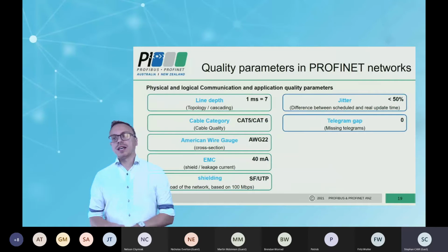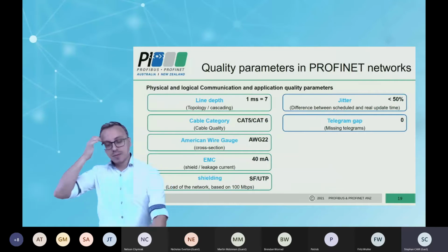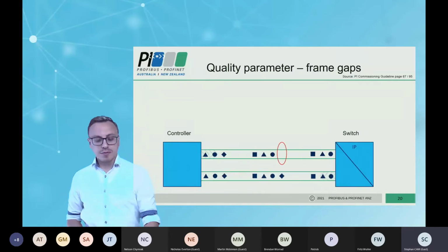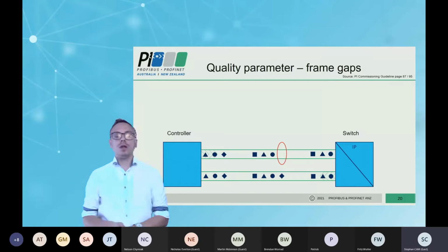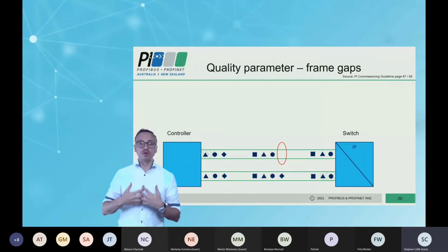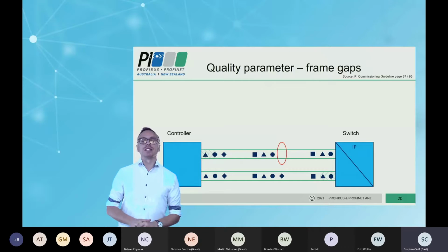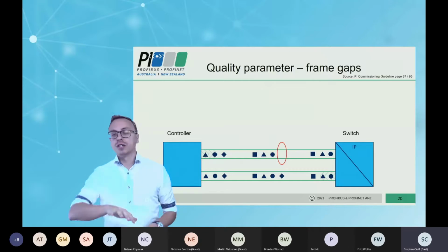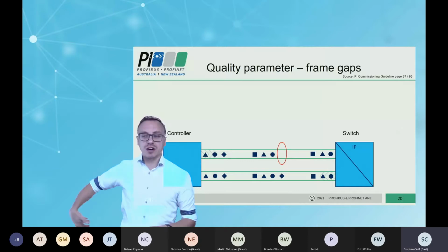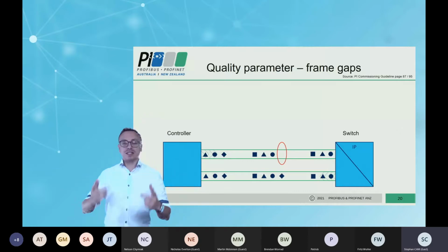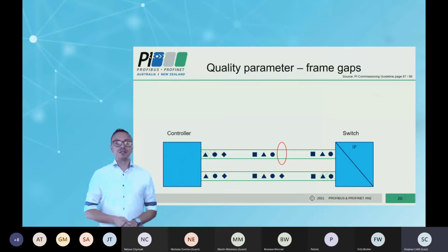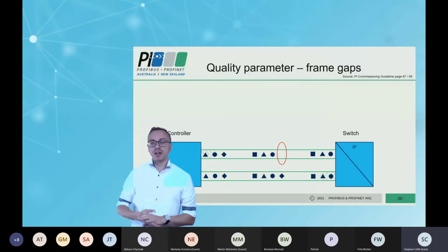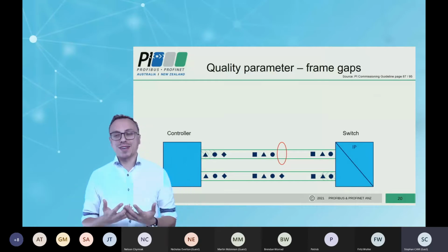Okay, the next thing is the telegram gap. That means if you have, for example, an error frame, or too much net load, as I said, the devices will discard frames due to overload. Or if you have an error frame, a destroyed frame, the devices will discard this frame. Because of your cyclical communication, if devices discard frames, you get a frame gap.